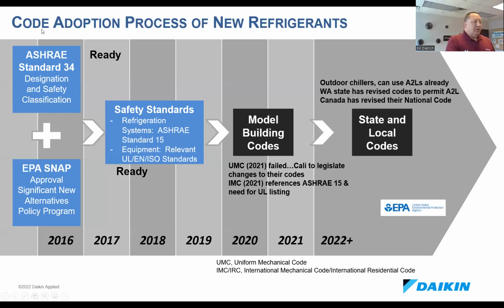When we look at how new refrigerants get into the code adoption process, we have ASHRAE 34 do their thing, and then the EPA also has to approve the use of that refrigerant for that specific application under what's called their SNAP program. This program really came about back in the 90s when we started doing the phase out of CFCs and HCFCs.